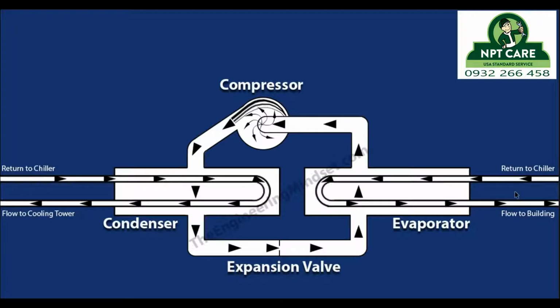So the water that's coming in is held within these tubes, and that keeps the water completely isolated from the refrigerant. The 2 never mix. The water comes in, passes through the tubes, and then leaves again. It does not leave these tubes. The refrigerant passes through, picks up the heat, and it just transfers that heat through the tube walls there. The refrigerant picks that up and then transfers that round to the compressor.